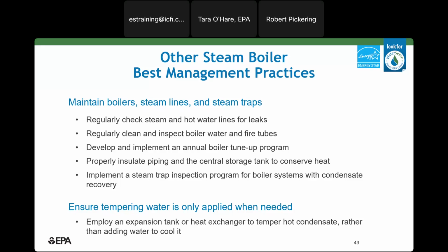One area that deserves careful attention and where we frequently see water savings opportunity is with the tempering water application. So tempering water is often applied where the hot condensate or blowdown is discharged to the drain. This could be on a boiler blowdown flash tank or condensate draining from a flash tank on a steam vent.